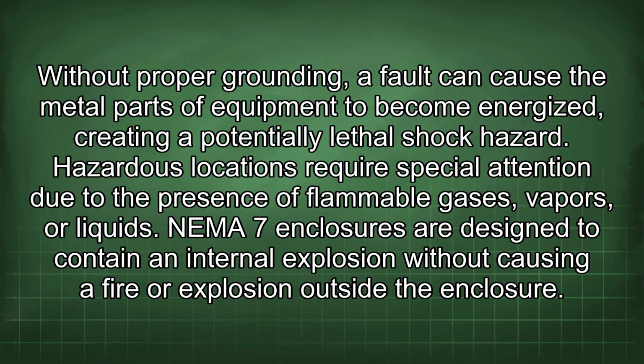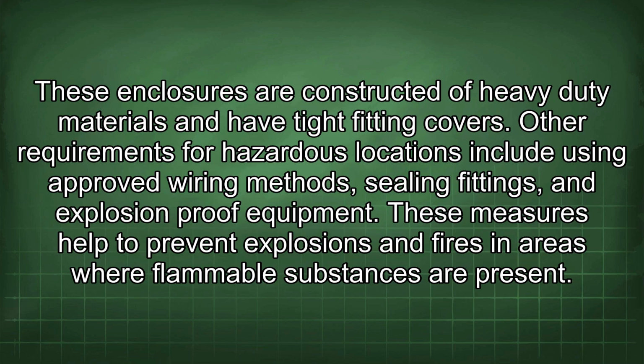NEMA 7 enclosures are designed to contain an internal explosion without causing a fire or explosion outside the enclosure. These enclosures are constructed of heavy-duty materials and have tight fitting covers. Other requirements for hazardous locations include using approved wiring methods, sealing fittings, and explosion-proof equipment. These measures help to prevent explosions and fires in areas where flammable substances are present.